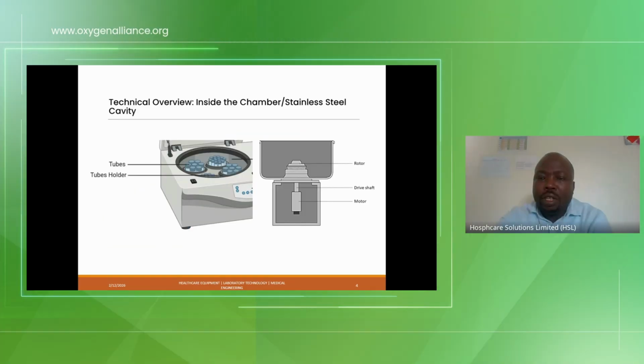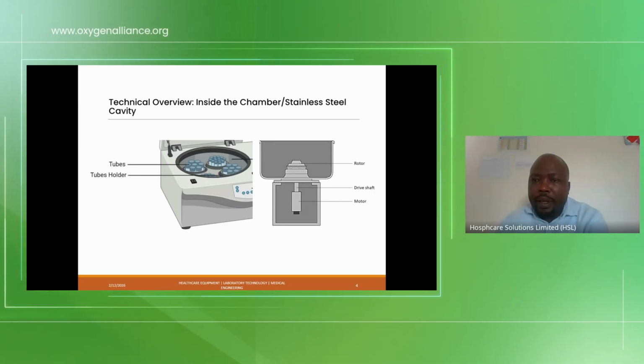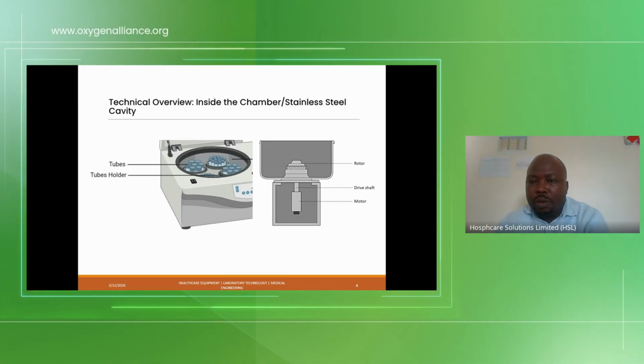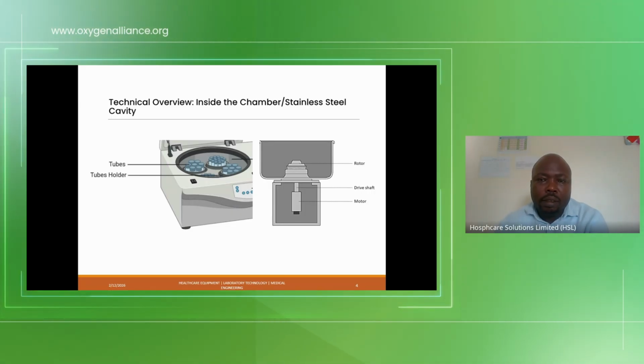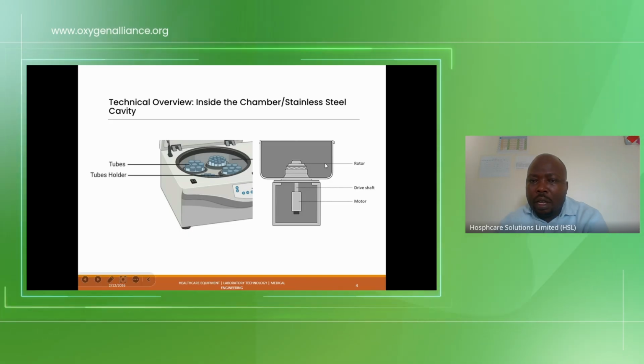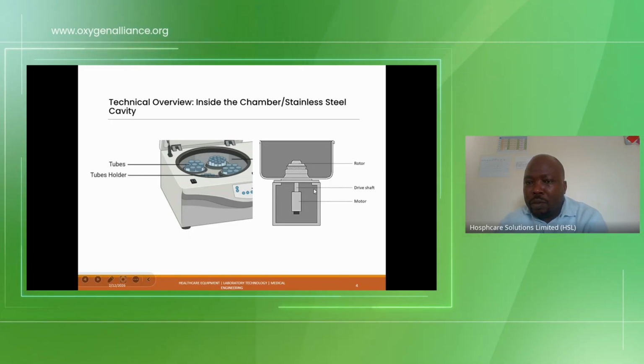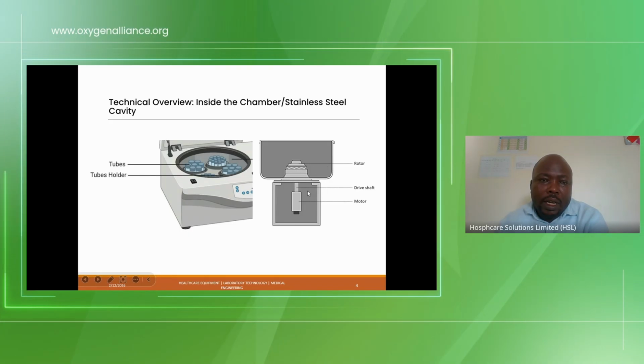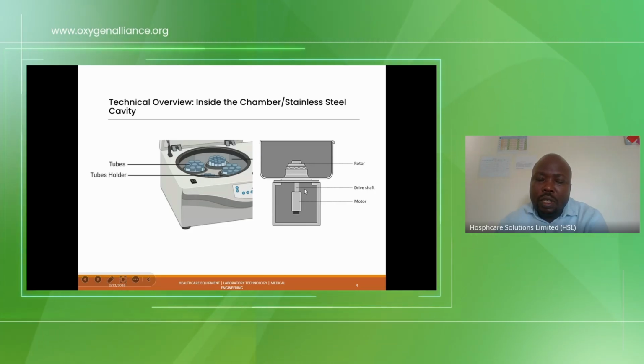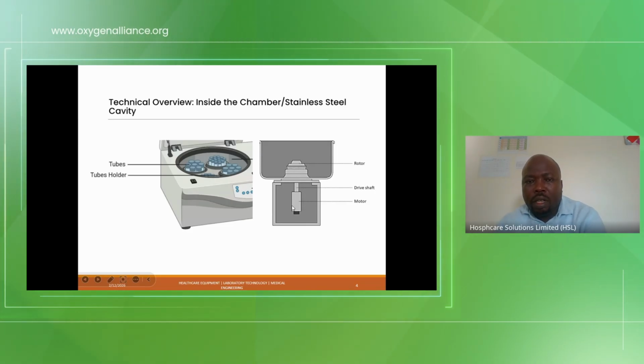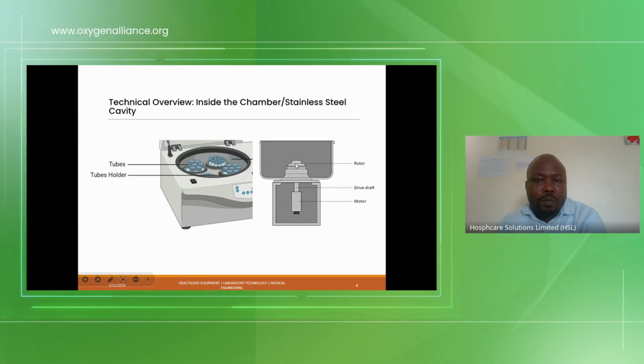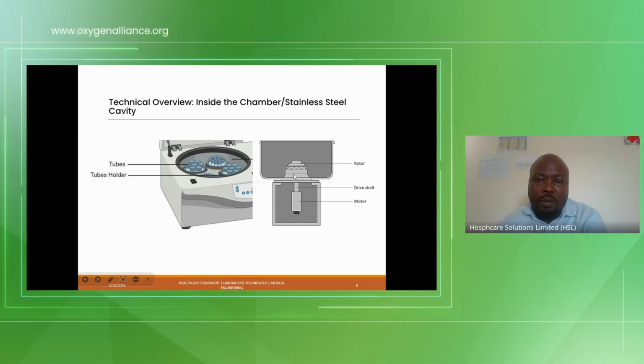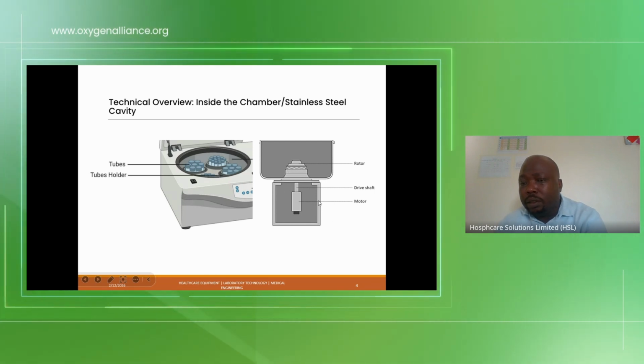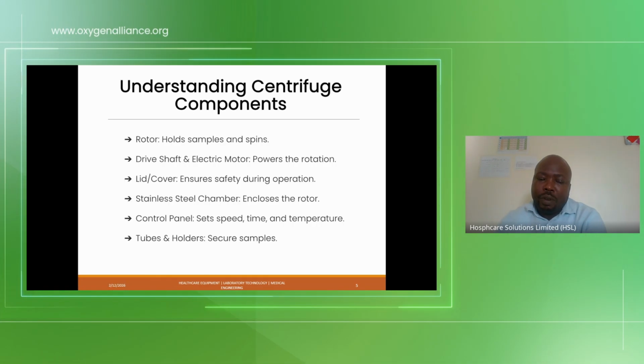A technical overview of a centrifuge machine, which I think is our area, is how the internal part looks. We have a rotor here, which is attached to the motor shaft, which in turn is holding the tube during the spinning. This is where the centrifugal force is coming from, the motor.